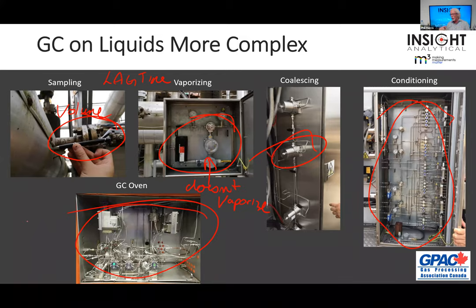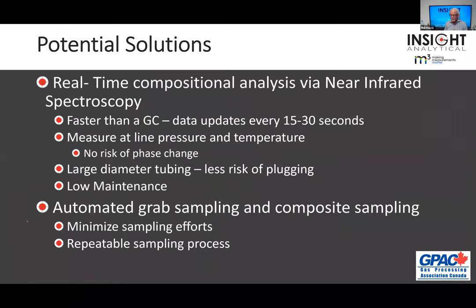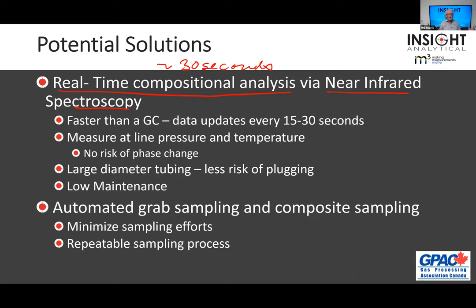This is one of the things we had the opportunity to work on with Fluor back in 2015–2016, when they started asking what kind of analyzers to put in the plant up there. One potential solution considered was real-time compositional analysis: updates every 30 seconds, fast analysis using a near-infrared spectrometer — way faster than a gas chromatograph, updating data every 15 or 30 seconds. Why is speed important? I can tighten my controllers. Instead of waiting for lag and thinking, 'Well, 15 minutes ago I should have turned the heat up,' we can do that almost instantaneously. This gives us better control.